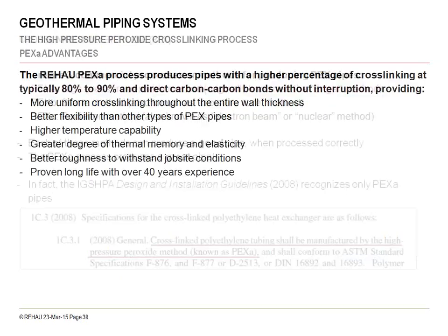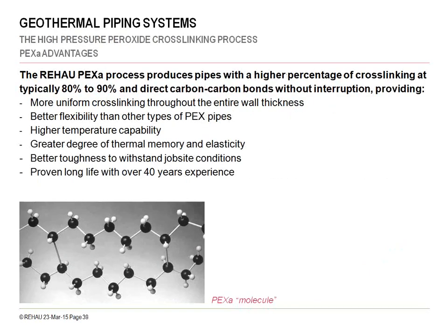And so, as I mentioned, if you go to the IGSHPA guidelines, you'll see that it's not just generically saying PEX, but it is saying PEX-A. And that has to do largely because of the connection method I'll talk about. And again, the 80 to 90% being the optimal percentage for PEX-A materials all the way through the wall thickness of the piping material.